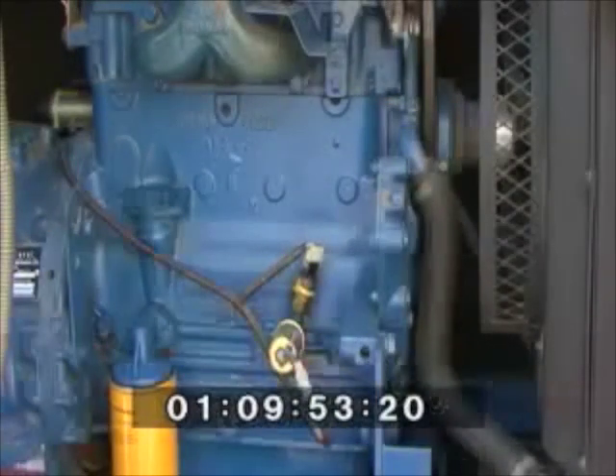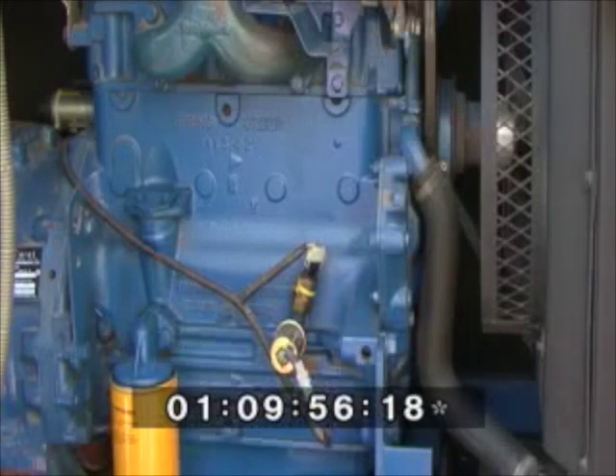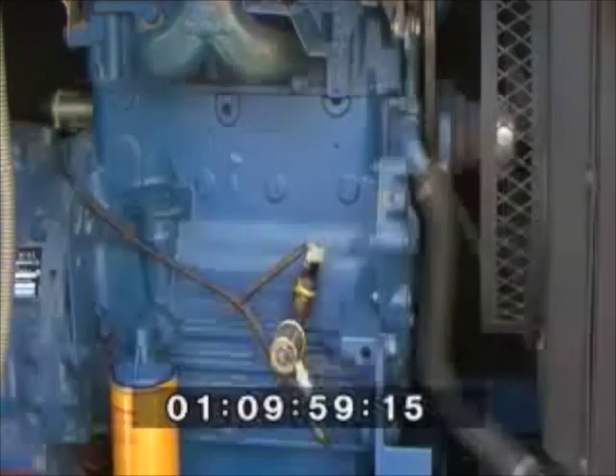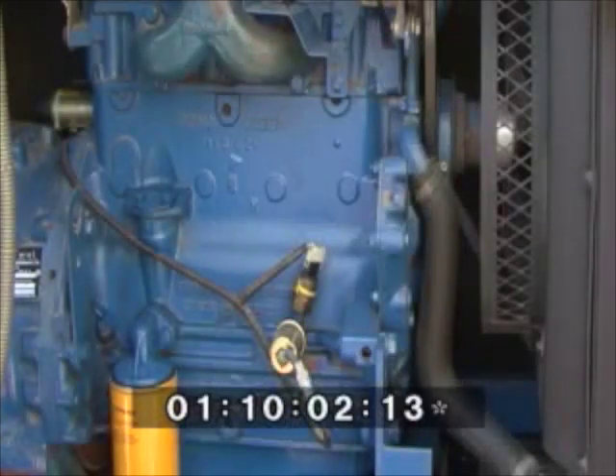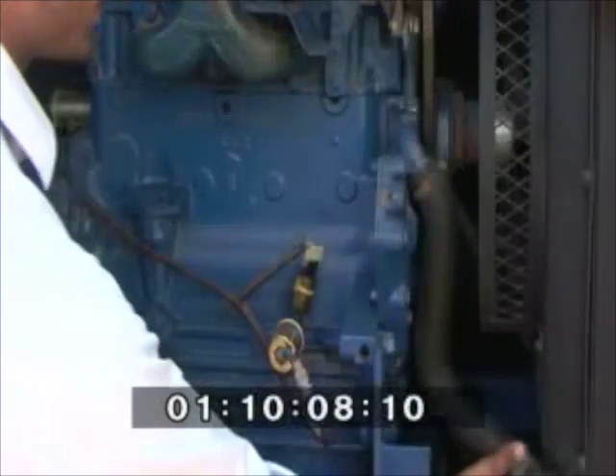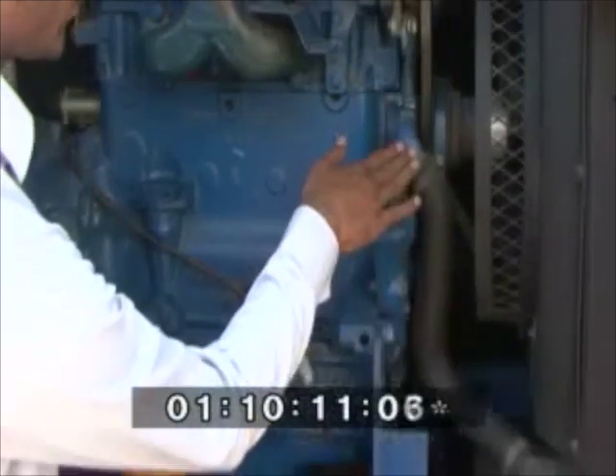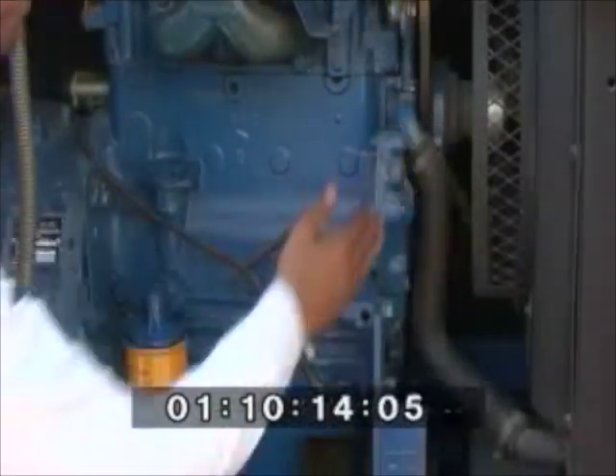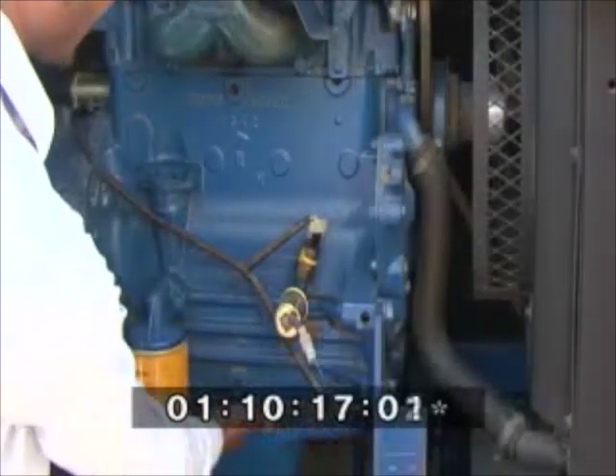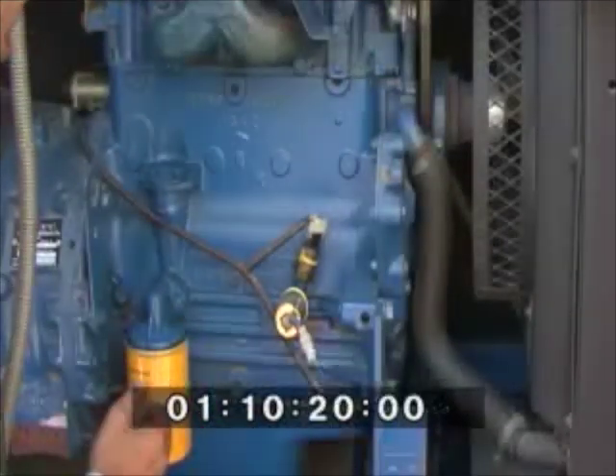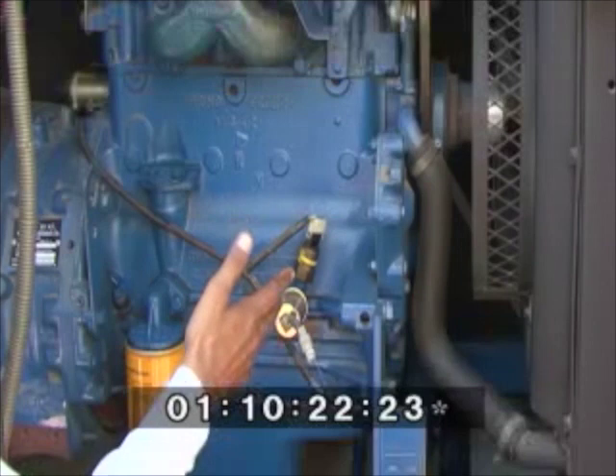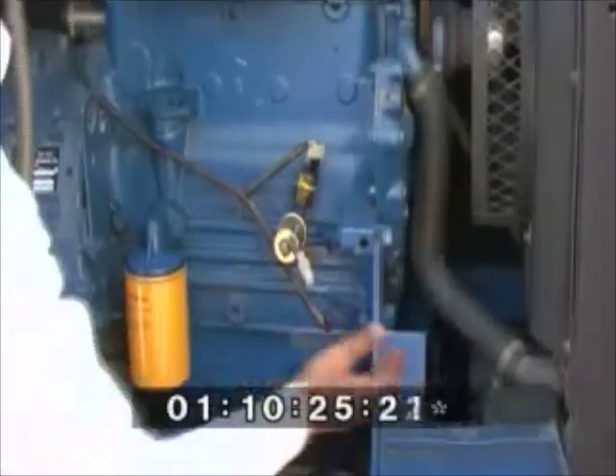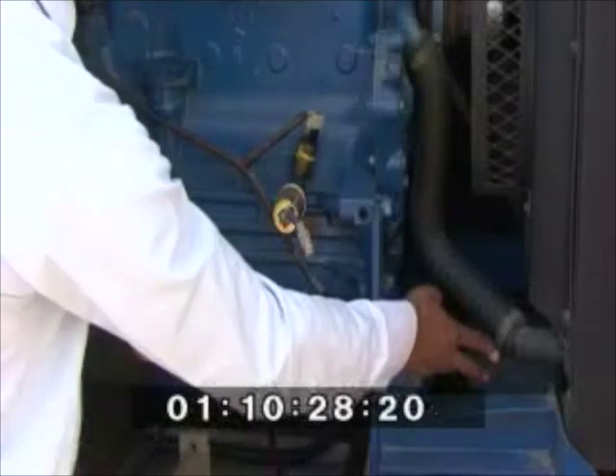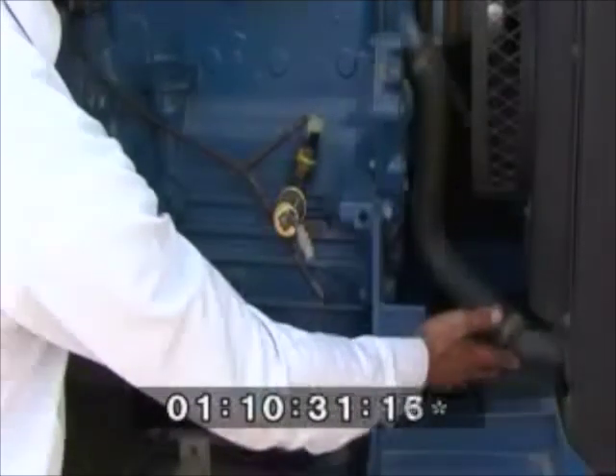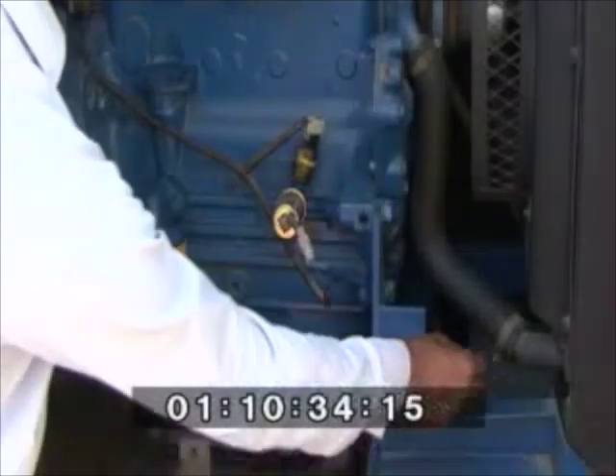Now we will check for leakage of oil in the DG. We will now see the points from where the leakages of oil can happen in the DG. We will check the point where there are cappings. Then we will check the chamber of the DG with our hands at the points you can see, and also look on the floor for stains. In case the leakage is from the caps, we will tighten the nuts to stop the leakage.